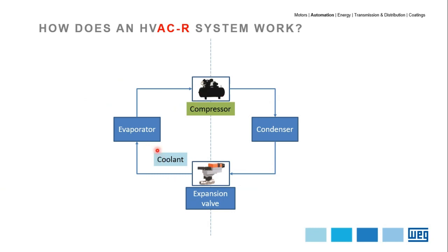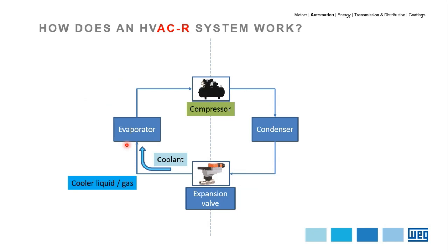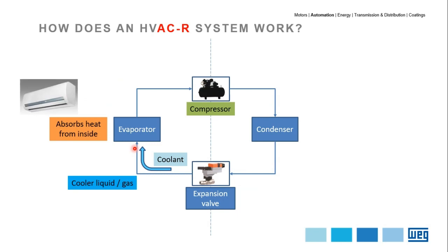Inside of the circuit there is a special gas called coolant, which is a refrigeration gas that changes dramatically in temperature and state as it goes through these stages. Starting after the expansion valve, the coolant is cool liquid and partially gas. Once it hits the evaporator — which is basically a serpentine coil — the coolant absorbs heat from the inside. It evaporates, as the name says, absorbing heat from the inside to transport outside.